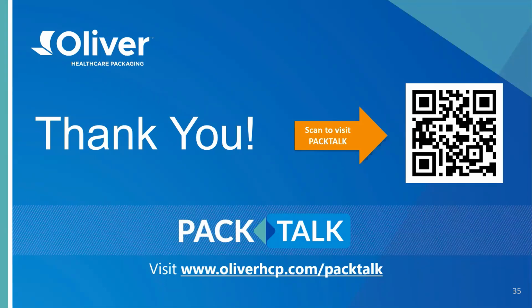And then finally, you continue on discussions about, if you still need a value, how do you determine or assess that value? People typically use ASTM F88 to assess seal strength when the actual user experience is different. As we mentioned earlier, design and opening features can influence that experience.